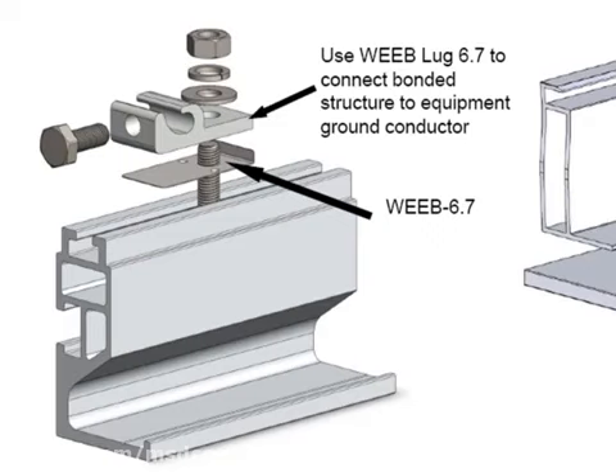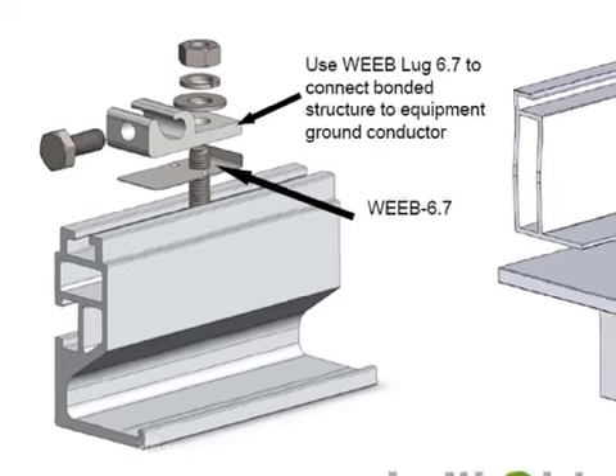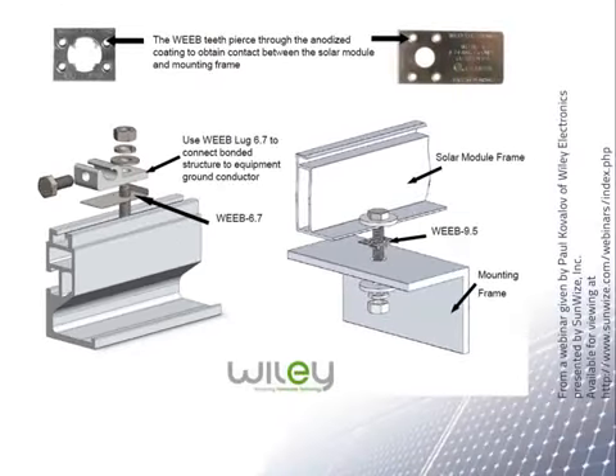WEEB connectors between rails and module frames connect the rails and frames to each other electrically, but they still need to be connected to ground. So at some point, you need to connect one or more of the rails to a copper wire. In the configuration shown here, a copper wire will pass through the slot on the left of the lug and make a connection with ground for everything that is connected to the rail.